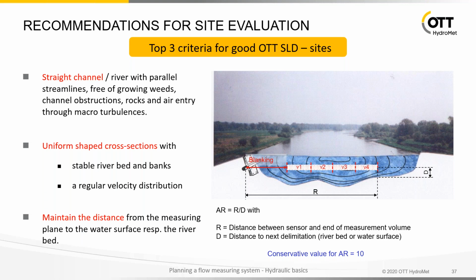We have good experiences, for example, with a site where we have 10 meters in width and just 15 centimeters water depth. And there's a 2 megahertz side-looking Doppler running, which is mounted 25 centimeters above the bottom. And we can really measure the full range. So this really depends on the instrument and also on the site conditions. The conservative value is 10. But in practice, you can have even 20 or more. But this requires a site test in advance.